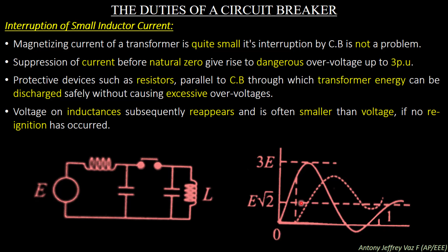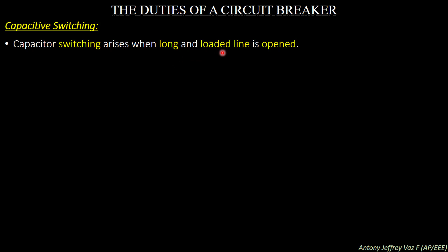Next one is capacitive switching. Capacitive switching arises when a long unloaded line is opened. Due to the Ferranti effect, the unloaded line carries a capacitive charging current, represented by the sinusoidal curve in the figure. We all know the Ferranti effect. For example, if the voltage measured at the start of the transmission line, near the source, is 5 volt, at the end of the transmission line it will be 10 volt. The Ferranti effect says that the voltage in a transmission line will be greater at the receiving end due to the capacitance effect of the transmission line.